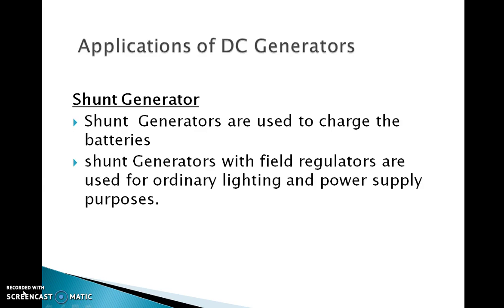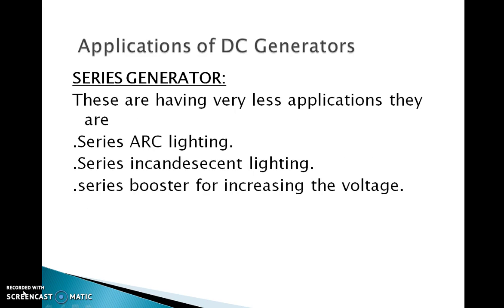Shunt generators with field regulators are also used for general power supply purposes. Series generators are not used for power supply because of their rising characteristics. However, their rising characteristics make them suitable as boosters in certain types of distribution systems, particularly in railway service. They are also used in series arc lighting, series incandescent lighting, and as series boosters for increasing voltage.